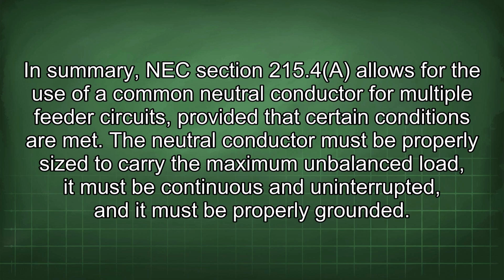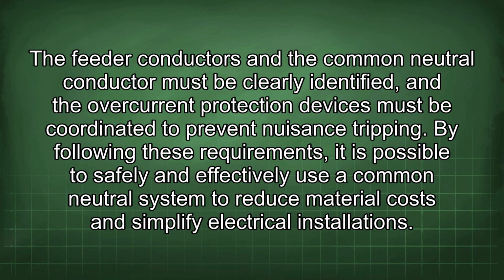In summary, NEC Section 215.4 allows for the use of a common neutral conductor for multiple feeder circuits, provided that certain conditions are met. The neutral conductor must be properly sized to carry the maximum unbalanced load, it must be continuous and uninterrupted, and it must be properly grounded. The feeder conductors and the common neutral conductor must be clearly identified, and the overcurrent protection devices must be coordinated to prevent nuisance tripping. By following these requirements, it is possible to safely and effectively use a common neutral system to reduce material costs and simplify electrical installations.